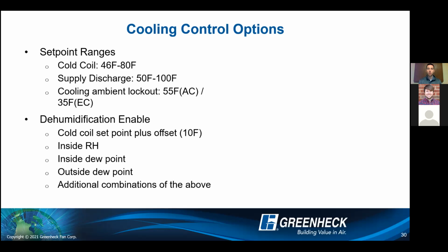Now, if we're in cooling only, or if we're in that type of situation and it's just cooling where we're not needing to drive that to a low dew point, the minimum overall supply discharge temp that you can get is 50 degrees, and then the maximum would be 100 degrees. So that is the range that you're seeing from an overall supply discharge set point.